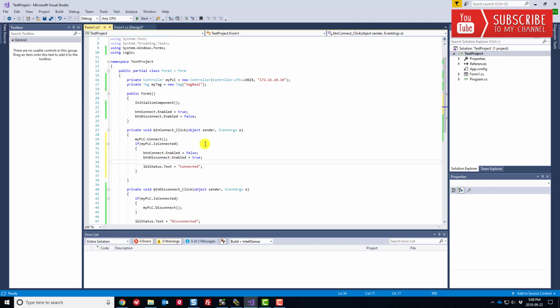We can do it on a change event. So for instance, if a tag value changes, then we trigger it to read. Or we could do an explicit read on some other trigger. So maybe a limit switch in the field gets actuated and we want to read a value or something. I mean, there are many different ways that we can set up to read and write tags. But for this example, I thought, you know what, let's do something a little bit more interesting and set up a continuous read on a tag at some sample rate that we define.